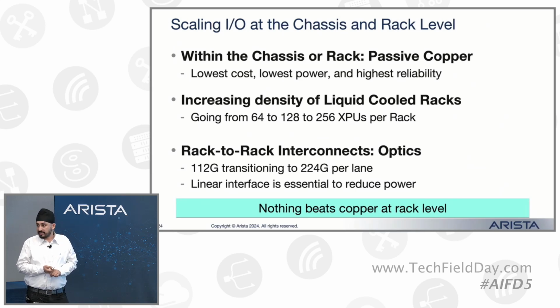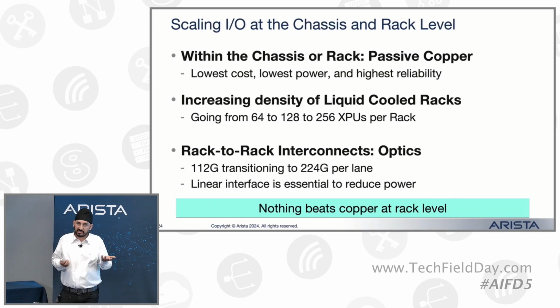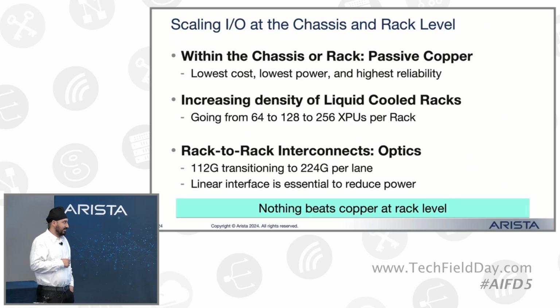Liquid cooling is helping racks go from higher density to the next higher density. If you look at the NVL72 rack from NVIDIA, it has 72 GPUs, 120 kilowatts. We think the next generation will probably double or quadruple that size - the number of XPUs you can put in a rack.